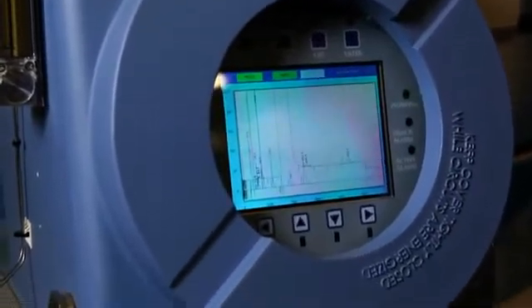As a bonus, with the C9 plus application, we can calculate the hydrocarbon dew point of the flowing gas stream. Now, custody flow meters cannot measure accurately a two phase flow. So we can use the gas chromatograph to calculate the hydrocarbon dew point of the flowing stream.